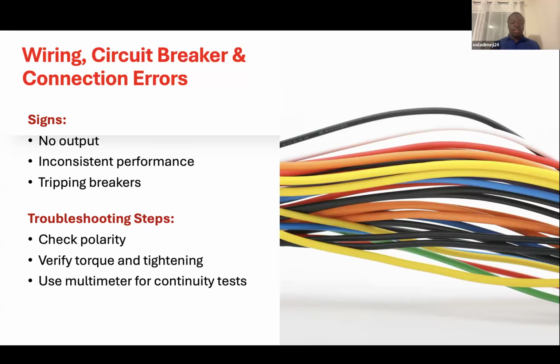you terminate a load cable and the cable is not well tightened to the terminal, you might have no output or partial contact, where the output is going off and going on, things like that. You also can use a multimeter for a continuity test, so that you check from one end to the other end: is there flow of current, what you're expecting from this point to this other point. That way you are able to troubleshoot problems with wiring, circuit breakers, or connection problems.